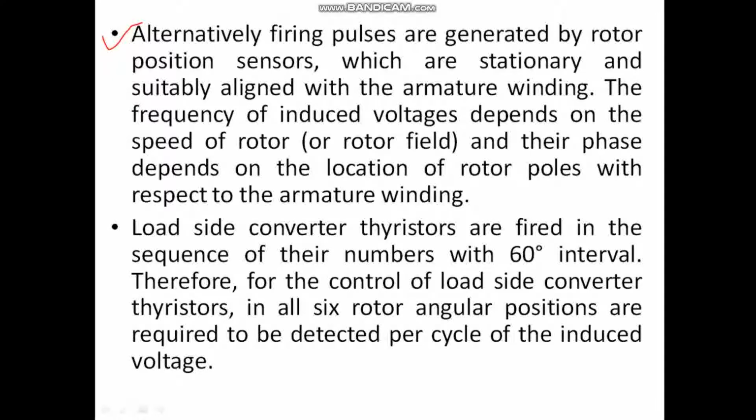Next, load side converter thyristors are fired in the sequence of their numbers with a 60-degree interval. In the first figure I have given you the numbering of the thyristors. So these are fired in the sequence of their numbers. This you already know. Therefore, for the control of load side converter thyristors, all 6 rotor angular positions are required to be detected per cycle of the induced voltage.